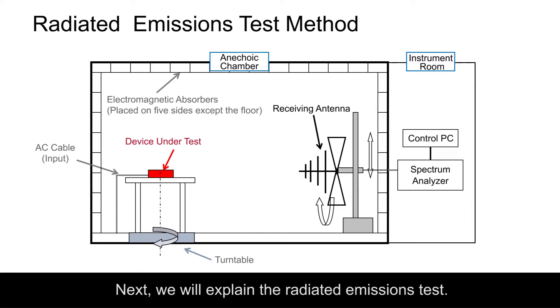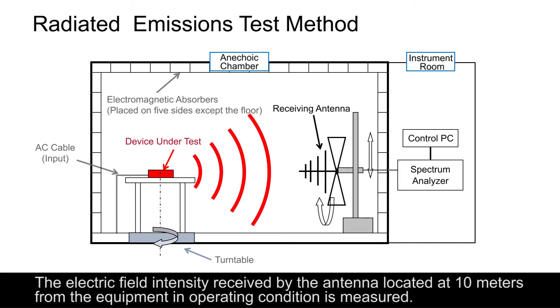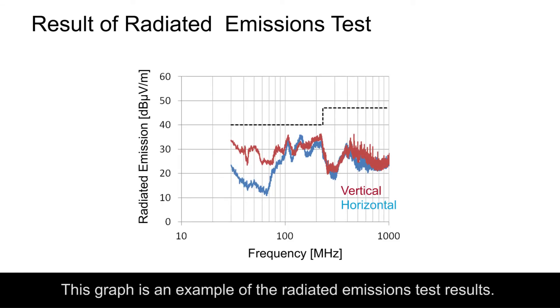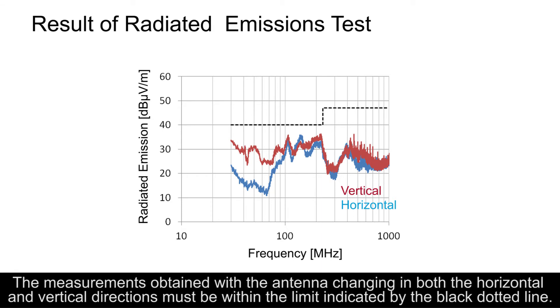Next, we will explain the radiated emissions test. In this test, the electromagnetic radiation level from the equipment is measured to make sure that it does not exceed the limit. The electric field intensity received by the antenna located at 10 meters from the equipment in operating condition is measured. Similar to the conducted emissions test results, the X-axis represents the frequency and the Y-axis shows the level of electromagnetic radiation. The measurements obtained with the antenna changing in both the horizontal and vertical directions must be within the limit indicated by the black dotted line.